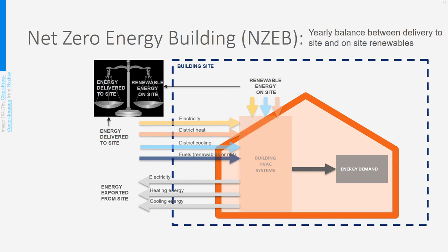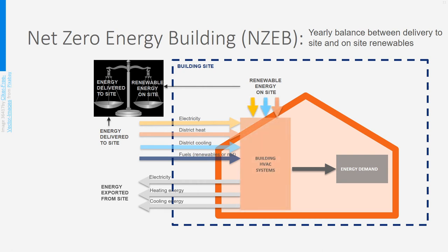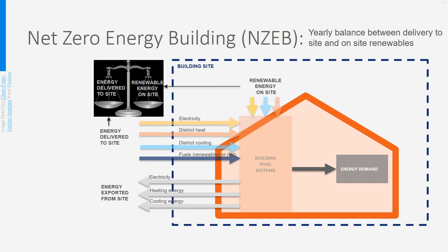There are many definitions of net zero energy buildings — it is not a standardized term, so make sure all partners in a project share a clear understanding. First, the renewable part of energy delivered to the site may or may not be taken into account — think of green certificates for electricity or geothermal district heating. Second, renewable energy generated on-site may be defined as energy produced and used on-site, or even as energy produced, used, and exported. Third, in some definitions not all energy is accounted for, but only electricity or only heating or cooling.